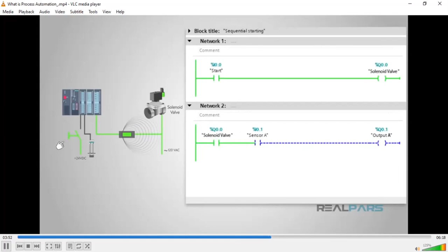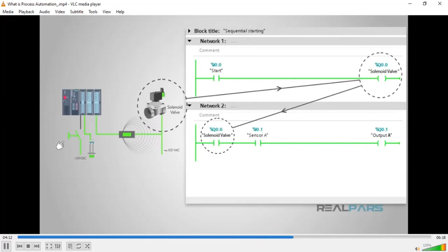Those inputs will go to a PLC, which will then make decisions based on how it was programmed. The PLC will then activate whatever output the program says to run. An output can be anything that does work, such as a motor, solenoid, heater, or a light. In an automated process, that output will typically be programmed as an input to the PLC and combined with other input devices or programming to keep the process running. With this programming, it can act like a chain reaction with one output device starting before the next is allowed to run. This is also called sequential starting.